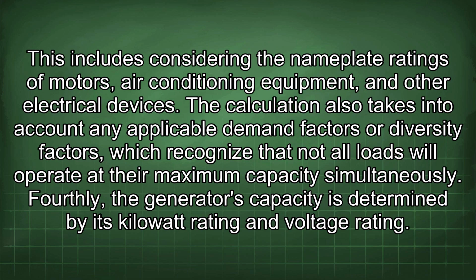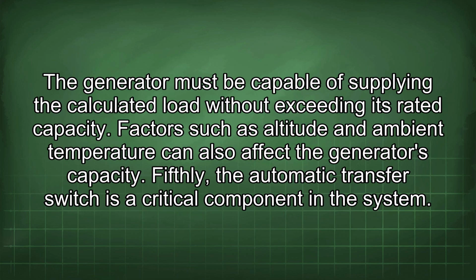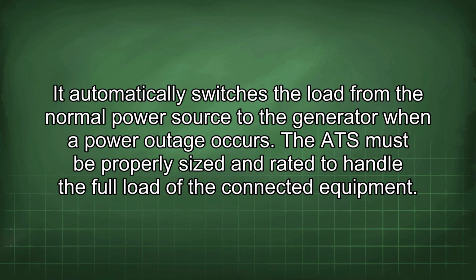Fourthly, the generator's capacity is determined by its kilowatt rating and voltage rating. The generator must be capable of supplying the calculated load without exceeding its rated capacity. Factors such as altitude and ambient temperature can also affect the generator's capacity. Fifthly, the automatic transfer switch is a critical component in the system. It automatically switches the load from the normal power source to the generator when a power outage occurs. The ATS must be properly sized and rated to handle the full load of the connected equipment.